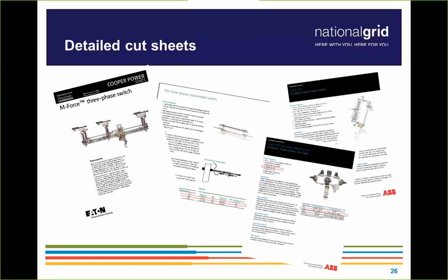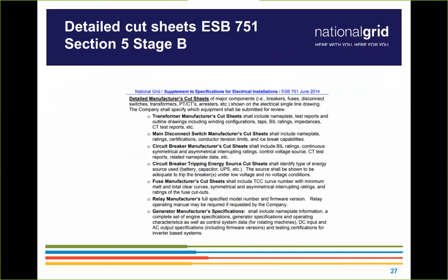Ice break for the operation of disconnects is important to us. All these things are defined as characteristics in our ESBs, or electrically defined parameters that are standard across industry, that we want to review to make sure that all the equipment that's being submitted is in fact going to meet our minimum standards and are going to be satisfactory for the specific installation at hand. Okay. And then data sheets are always a big question amongst the developers and customers. So again, if you can go to ESB 751, and there's definitions there, or at least some input on what's required for data sheets, what it should show, so on and so forth. So please refer to that.